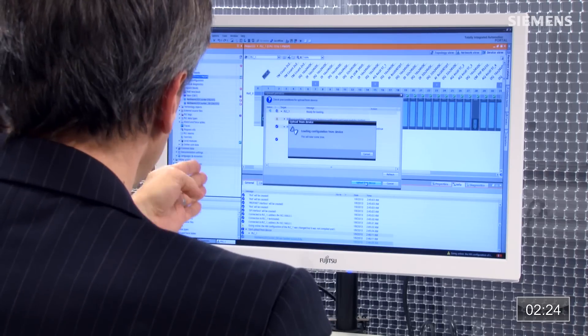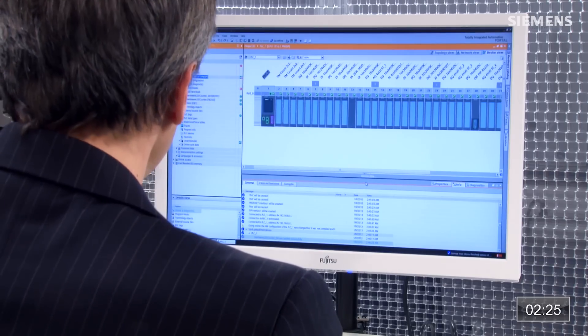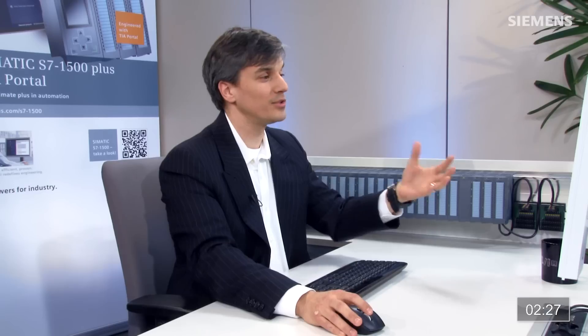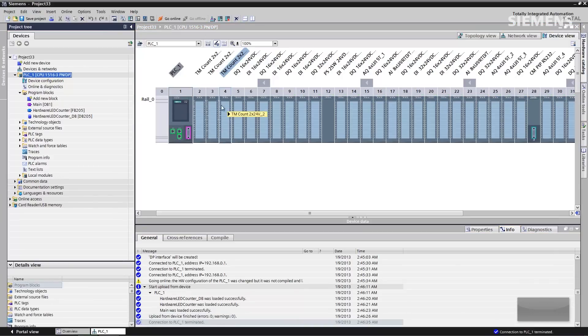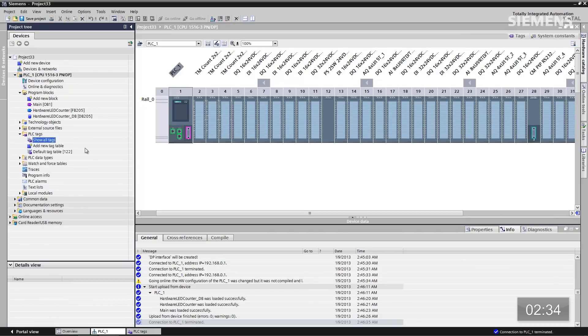Now it's going to go grab everything from a program standpoint and bring that back into the project in offline mode. Once it has, you'll notice in this tree structure everything will go green — that means we have everything from the actual CPU. I then click Go Offline, the orange bars go away. Now I can come down to PLC tags, open them up, and show all tags.